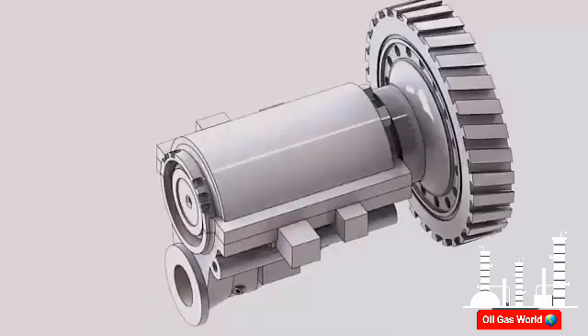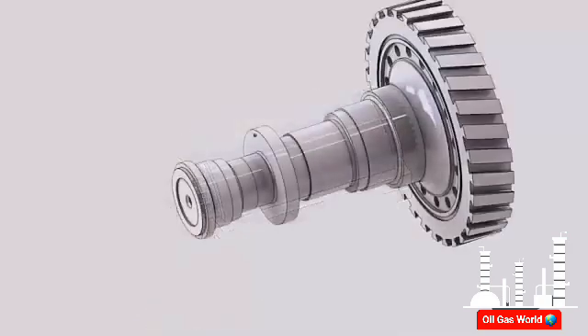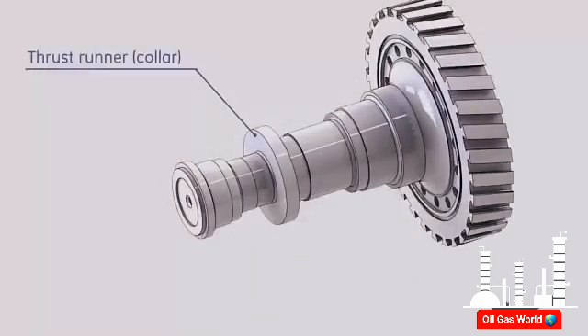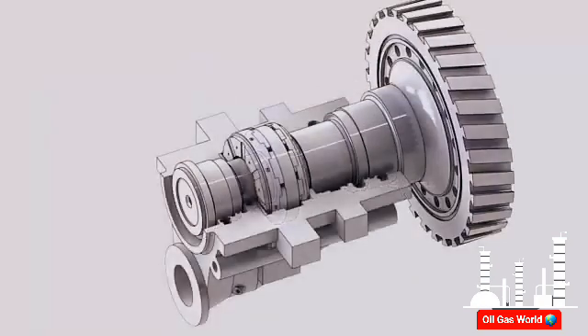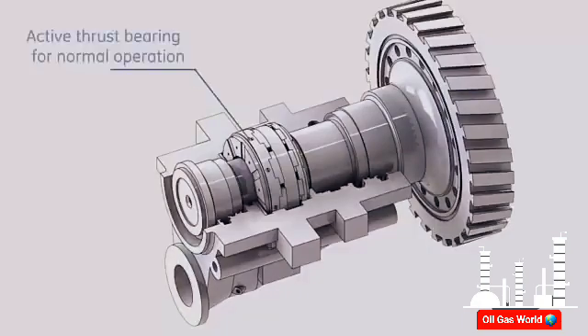The thrust bearing major components are the thrust runner, which is integrated in the compressor rotor forward stub shaft, and two thrust bearings. During normal operation of the gas turbine, the sum of axial forces induced by the airflow on the compressor stages and the hot gases flow through the turbine stages tend to move the rotor in the upstream direction, so that the active thrust bearing is located on the forward side of the thrust runner.